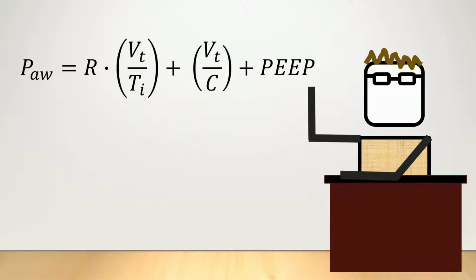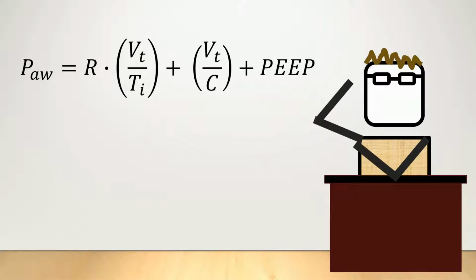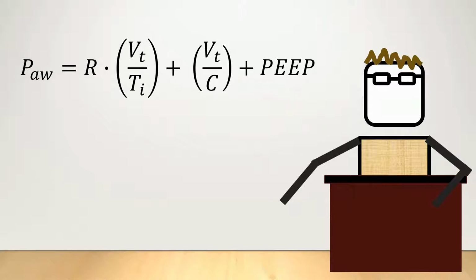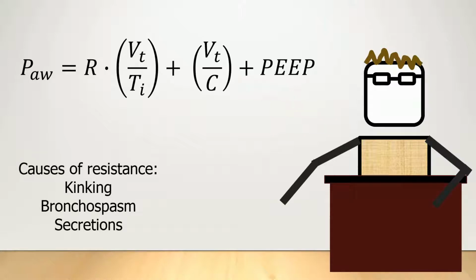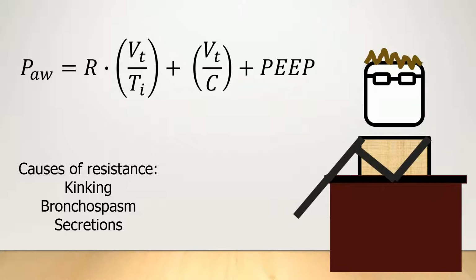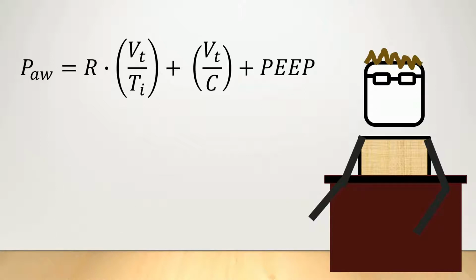The equation of motion can guide us in sorting out this problem by reminding us about the causes of airway pressure. The airway component is airflow and resistance, and in general, the airflow is not an issue, and usually it's the resistance. Causes of increased airway resistance include kinking in the tubing, bronchospasm, and secretions, which can occur in either the tubing or in the lower airways.